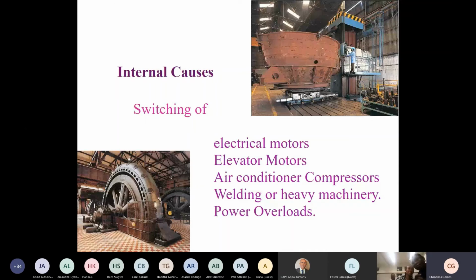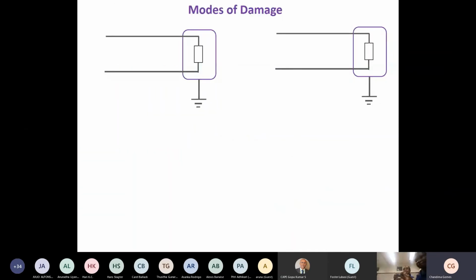And most often, all these transients are covered under lightning protection, because when you give solutions for lightning protection, most of these transients are also being covered, except for a few, like the transients generated by power factor correction capacitor banks. They can bypass the SPDs. Now, how can lightning cause damage?